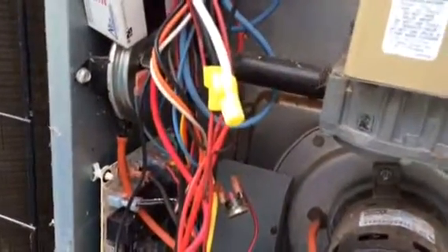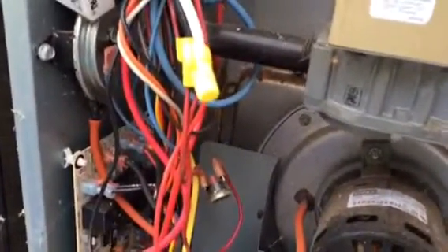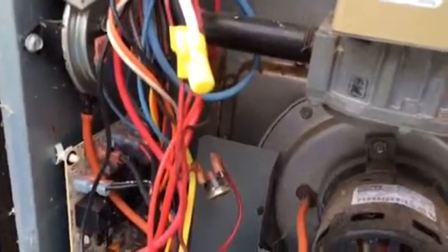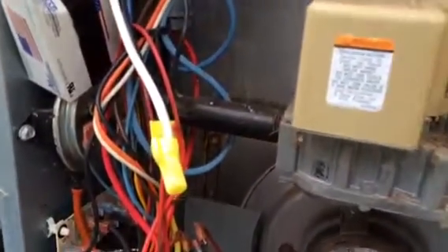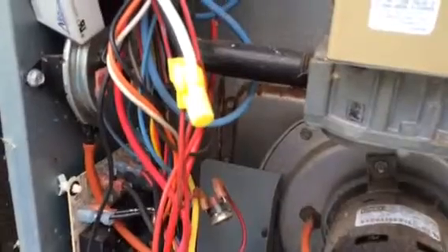And when it reaches that max set temperature, which for this one here is 300. And like I said, the other one that I bypassed is 350. So the temperature is going to be at a higher cutoff now. The second reason is that the rollout switch is going bad, and it's got a bad connection.